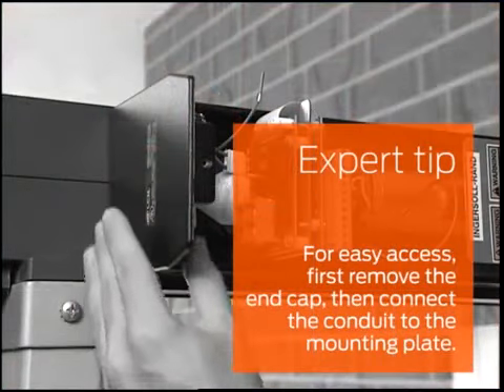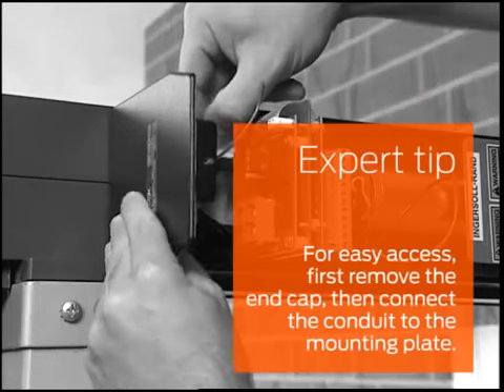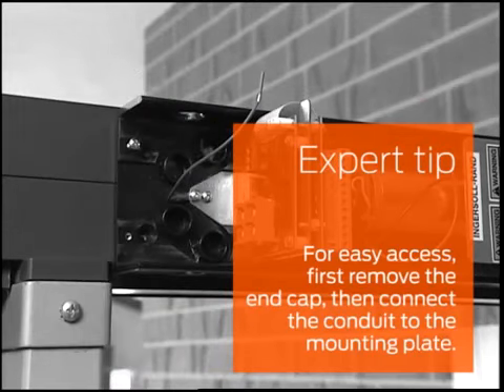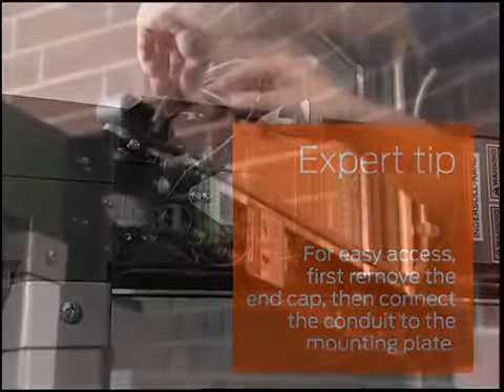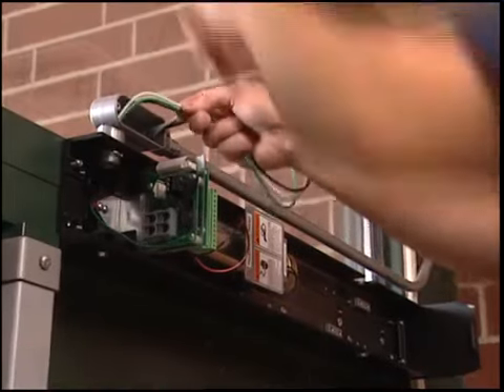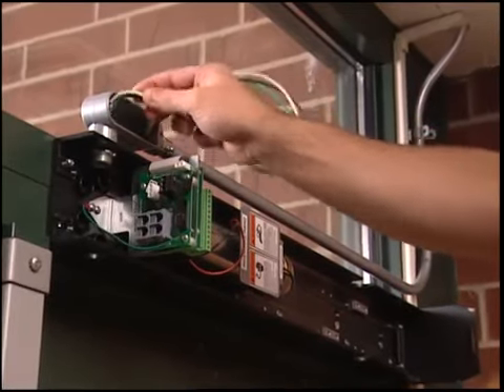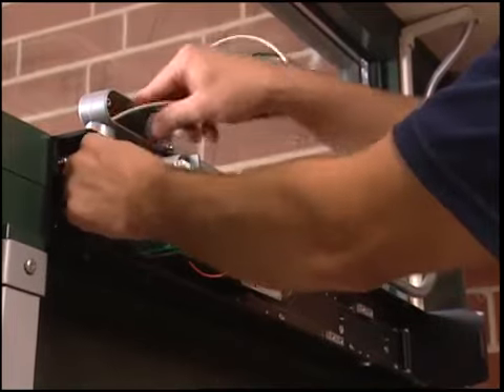For easy access, first remove the end cap, then connect the conduit to the mounting plate. Next, thread the wires through the conduit body and attach the 1/2 inch conduit to the mounting channel if necessary for your site.